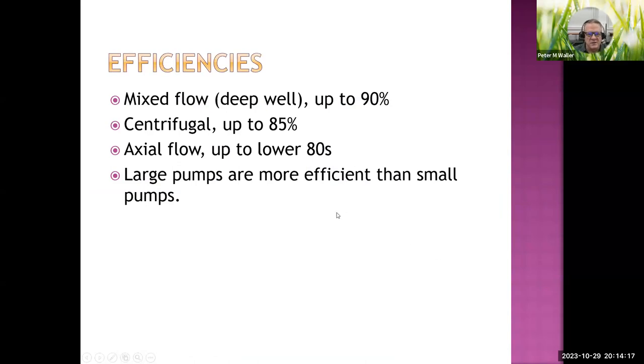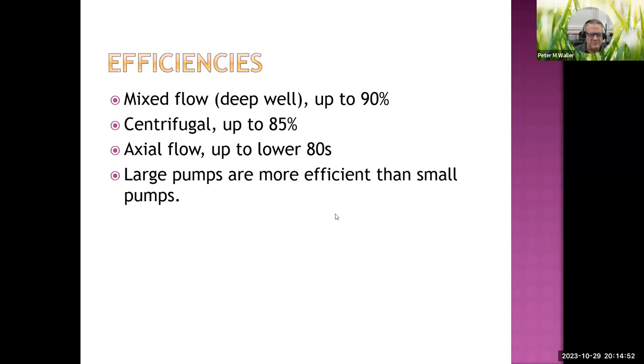Pump efficiencies are mainly dependent on pump size. Large mixed flow pumps used in deep wells can be up to 90% efficient — meaning water horsepower out divided by electrical power in. Centrifugal pumps can reach up to 85% efficiency, and axial flow pumps, where water passes straight through, can reach into the lower 80s.